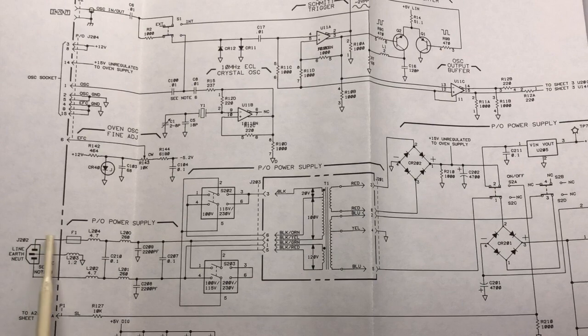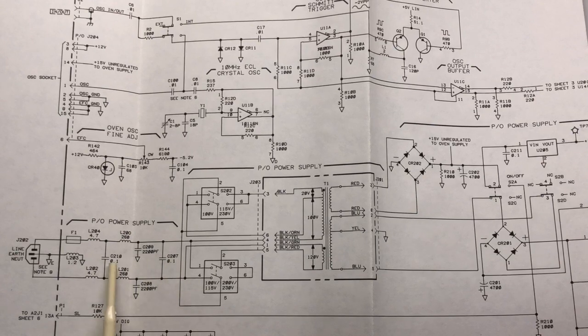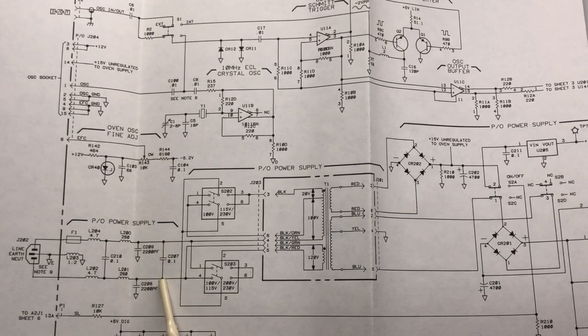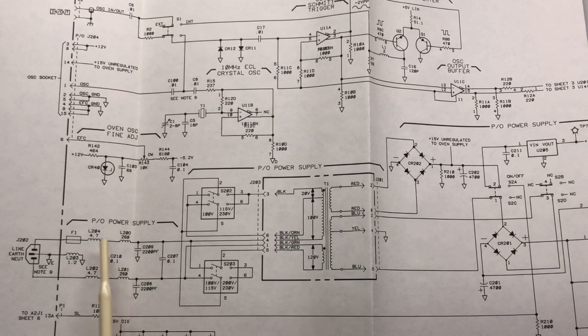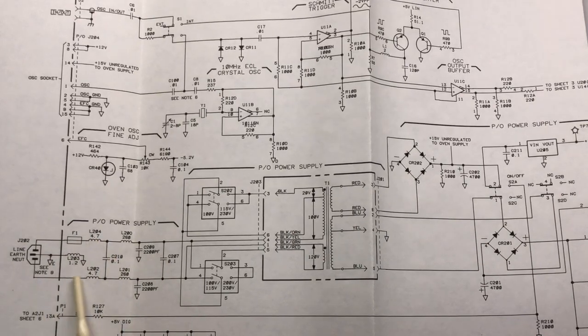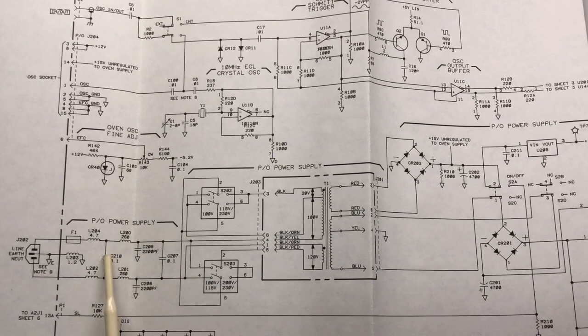So right here the hot AC line comes into F1, which is the fuse. And then we have these inductors right here, and then the 4 safety capacitors. So this circuit is providing filtering on the AC line, noise removal, RF removal, things like that, so that the AC coming into the instrument is clean and does not have any noise on it. Now you can see that C210 and C207 are 0.1 microfarad capacitors. And you can see that they're connected directly across the AC line. So anytime you have capacitors that are across the AC line, so we have the hot up here and neutral down here, so directly across the line, those need to be the X class capacitors, very often X2 rated capacitors.